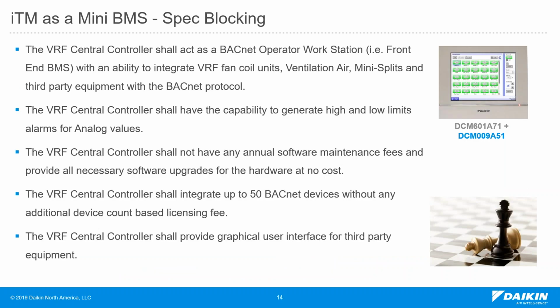To use the BACnet client in a spec blocking, we can also use sentences like: VRF controller shall act as BACnet operator workstation. BACnet operator workstation means we are the front end, whereas other competitors have to go to an actual full-blown BMS system to do that job. With the ability to integrate VRF, fan coil units, ventilation, air, mini split, and third-party equipment with BACnet protocol. This is very good in a small or medium project that requires a BMS, and here you can use the ITM, the VRF system, to block competitors with the use of the BACnet client function. You can use this sentence and work with the engineer again.